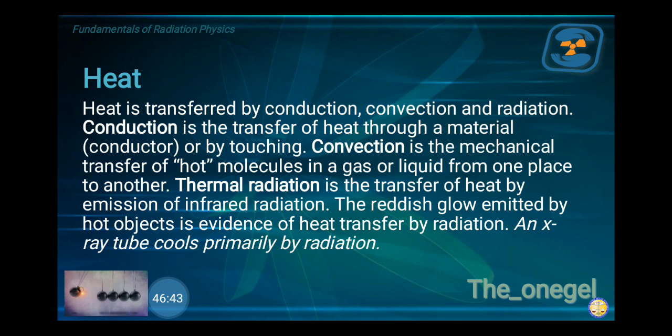So we have thermal cushion. That is why we have Diala oil number 5 in the X-ray tube. Thermal cushion, so we absorb the heat. Because in the X-ray tube, out of 100% of the projectile electrons, only 1% or less is converted to X-rays and 99% is converted to heat. That's why. Okay.